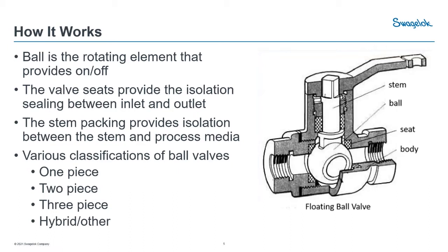One other thing to note on isolation and sealing is the stem packing. The stem packing is a seal that sits up top and basically seals your process media from the outside atmosphere. We see a lot of stem leakage in surveys across all valves, not just ball valves. We want to pay attention to that packing — we need to know what it's made of, that it's compatible with our system, and maintain it just like the rest of our process parts.